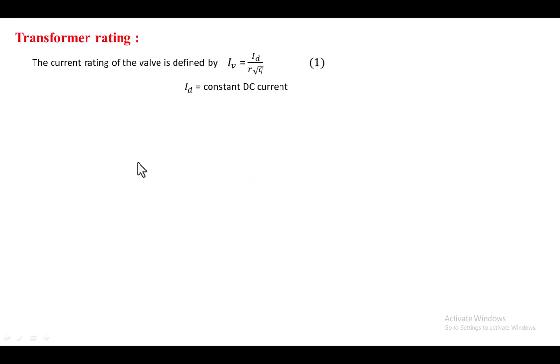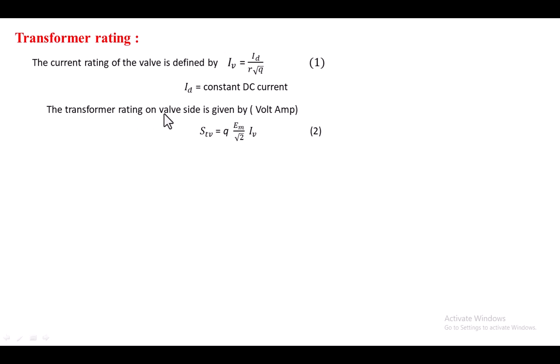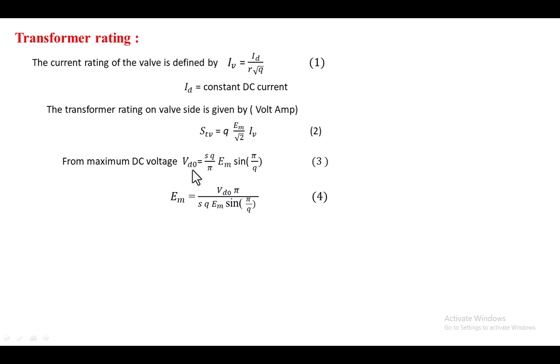For transformer rating, the current passing through the valve is defined as Iv = Id / (r × √q), where r is the number of commutation groups connected in parallel, q is the number of devices in a commutation group, and Id is the constant DC current. The transformer rating in volt-amperes equals q × (Em / √2) × Iv. We already know Iv, and the maximum converter voltage is Vd0 = (sq/π) × Em × sin(π/q).